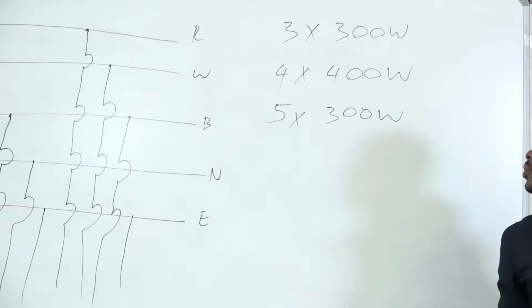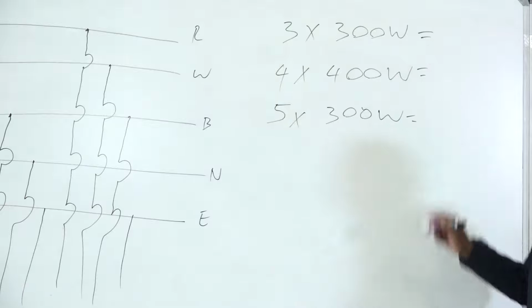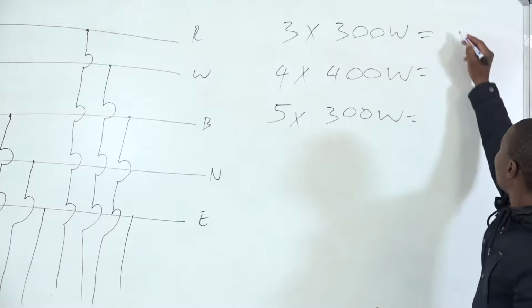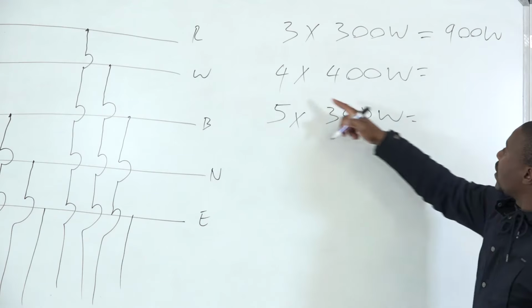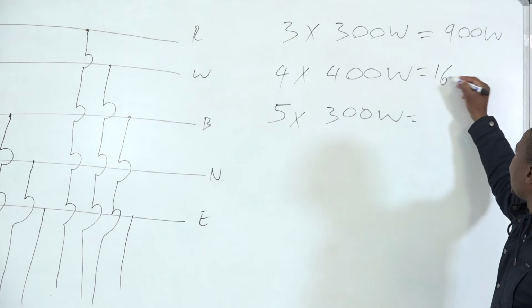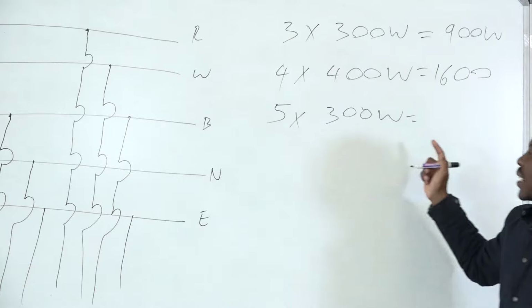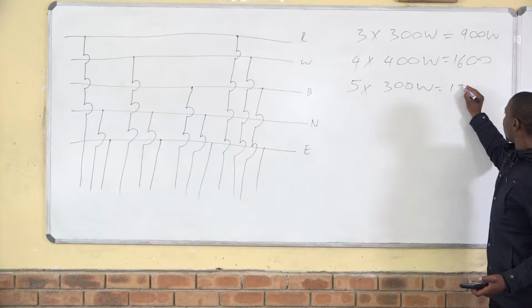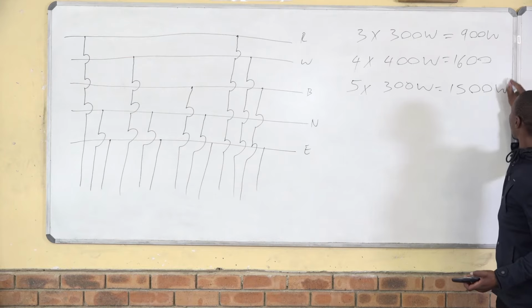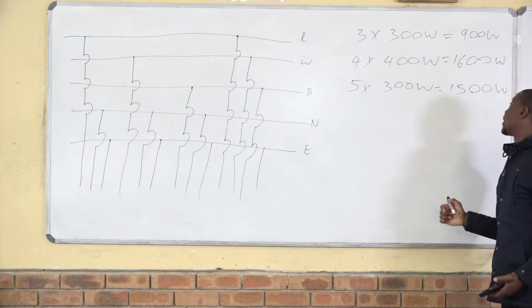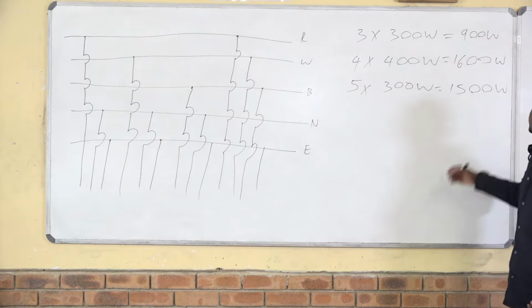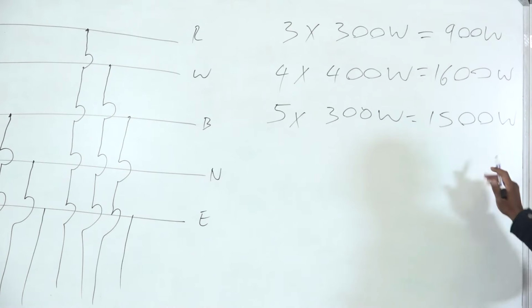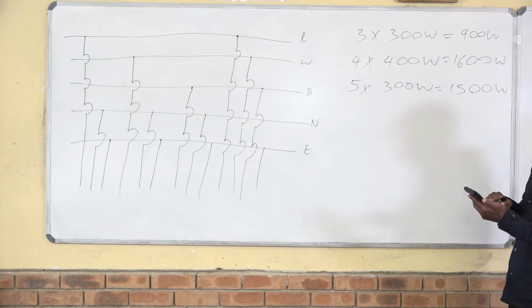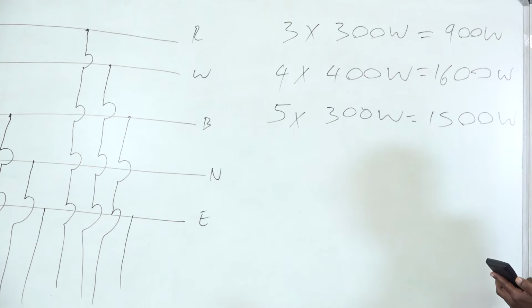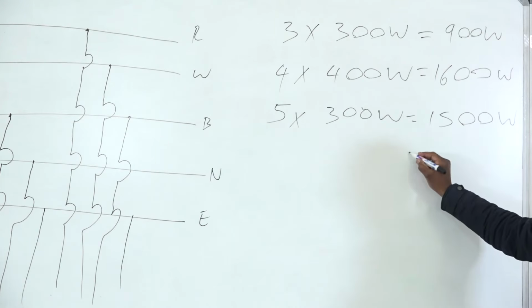So what you will be requested to do is to add all these wattages. You will say 3 times 300, you get your 900 watts. You say 4 times 400, you get your 1,600 watts. You say 5 times 300 watts, you get your 1,500 watts. And then now, since you have these totals, you want to balance them in a 3-phase system. You add these total wattages. You will say 900 plus 1,600 plus 1,500, and then you get 4,000 watts.